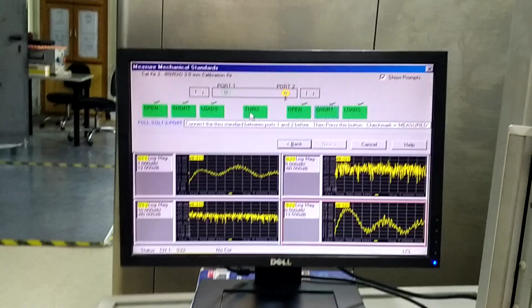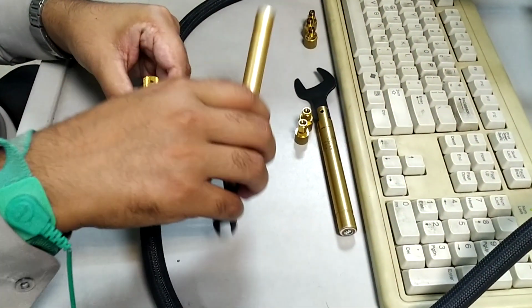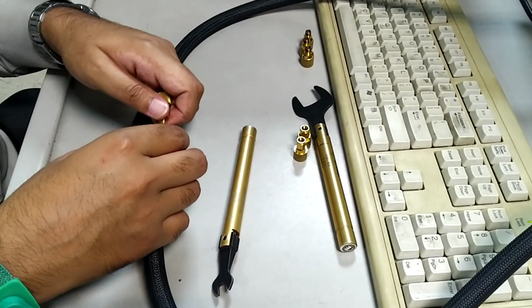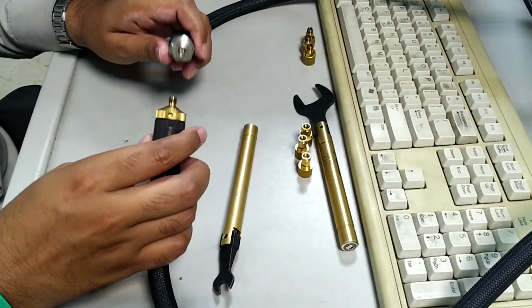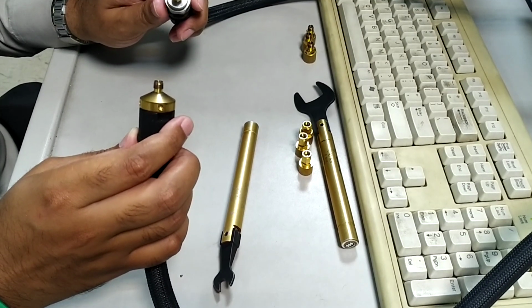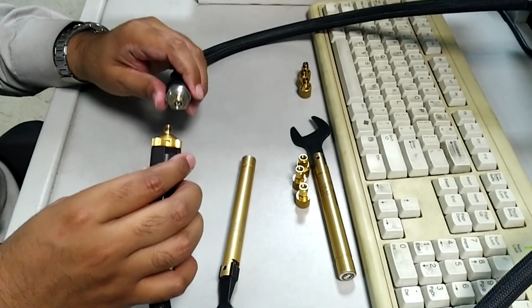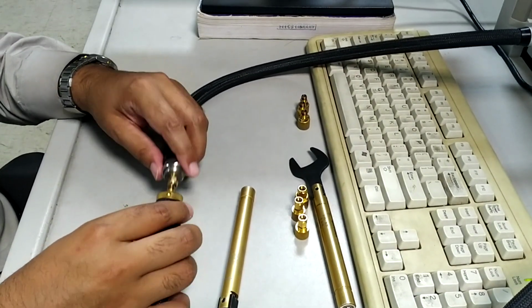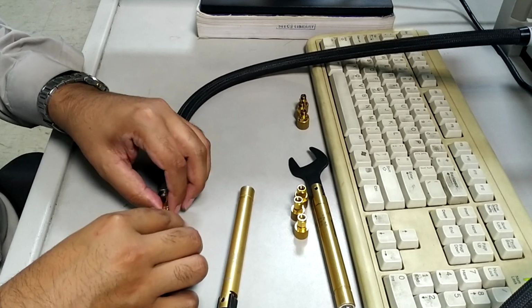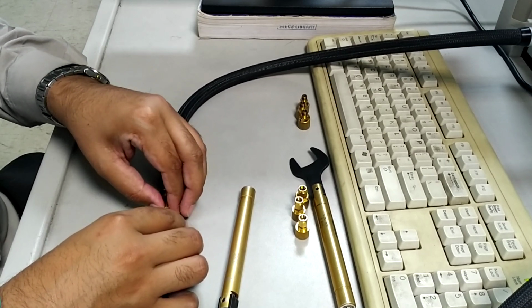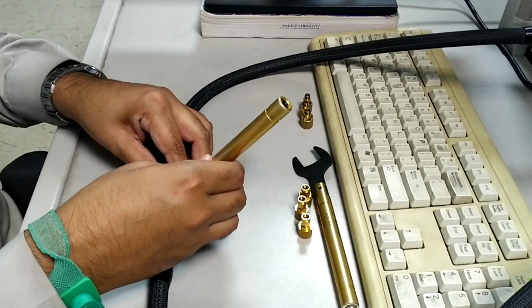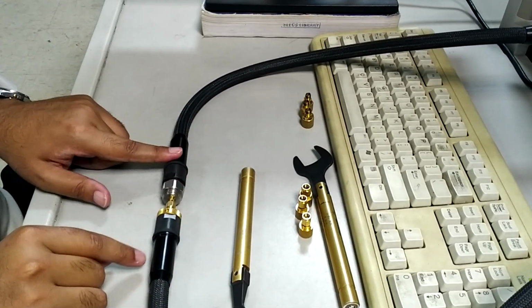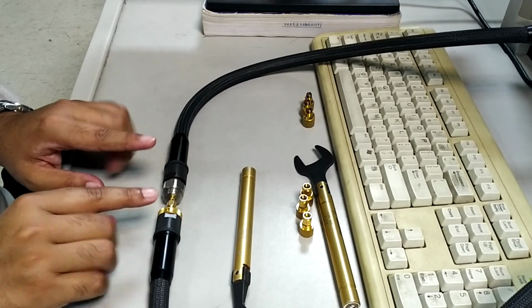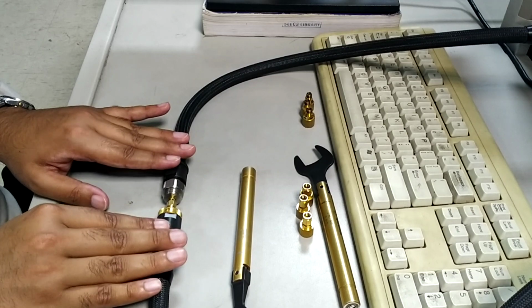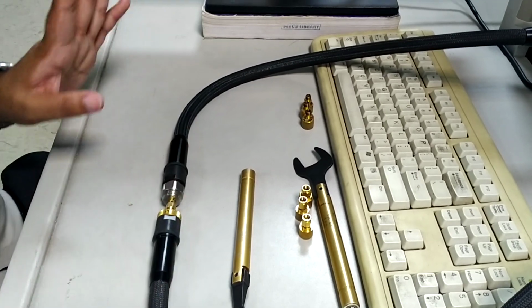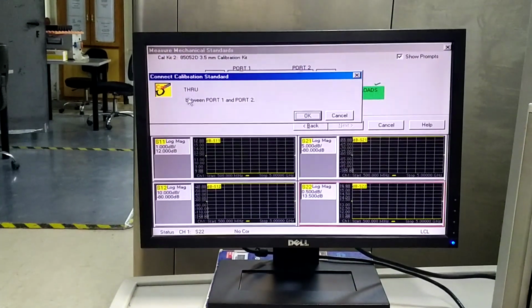So let's perform a through connection now. As you can see, these two cables, as I mentioned earlier, have opposite ends, which means I can perform a direct through. So in our case, this through will be a zero length through. So I just connect them together, put them here, and just connect them. You can see this is port number 1, this is port number 2, and they are connected directly. So the through that has been used in this calibration technique is a zero length through. So now I go to the screen and press the through between port 1 and port 2.